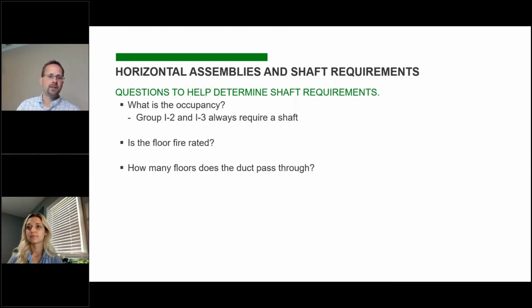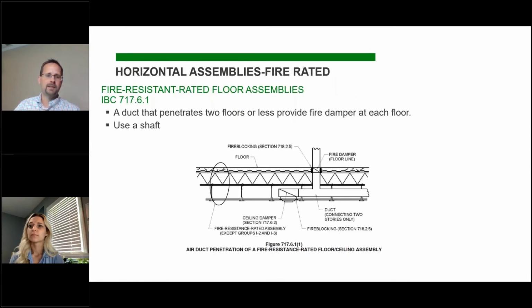The other question is, are the floors rated? Because there's two different sections you go to, whether your floor is a rated floor or it's not. And then how many floors does that duct system pass through? So the first thing we're going to talk about is a penetration of horizontal assemblies for a fire rated floor.